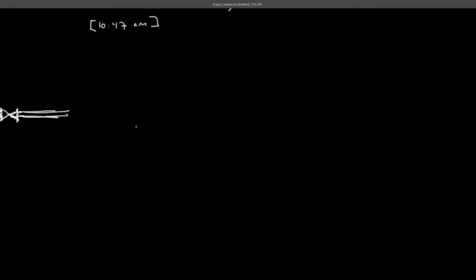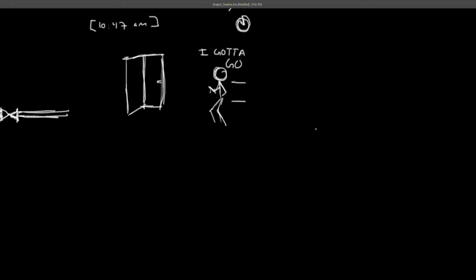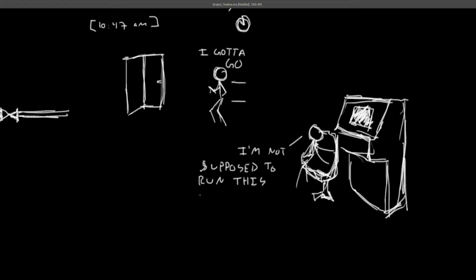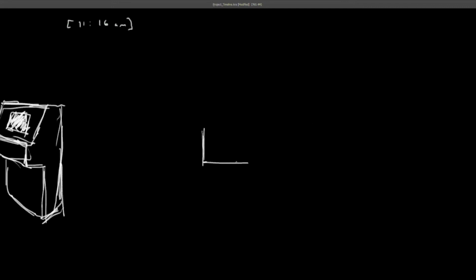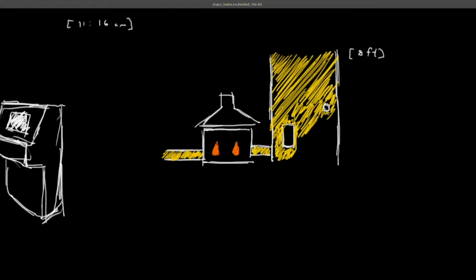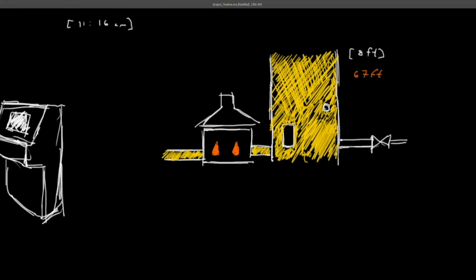10:47 a.m. The day supervisor left in the middle of the startup procedure for a family medical emergency without notice, violating BP's procedure of assigning a substitute supervisor in the CCR during his time away, leaving one control operator around 3 units, with one of them being in the ISOM unit during the startup, which required close attention. 11:16 a.m. 2 additional burners are lit while the level in the tank is reported as 8.65 feet. The actual level is close to 67 feet.